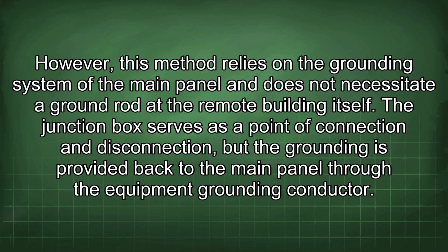However, this method relies on the grounding system of the main panel and does not necessitate a ground rod at the remote building itself. The junction box serves as a point of connection and disconnection, but the grounding is provided back to the main panel through the equipment grounding conductor.